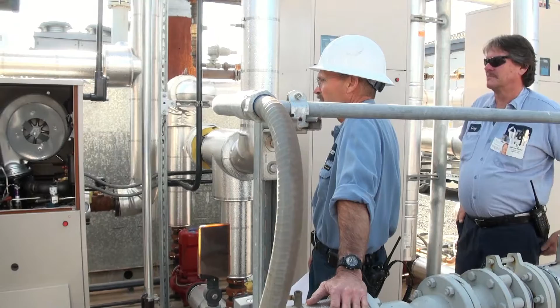Yeah, I know what you're saying, because the pleat is going to get water in it because you're so low at the bottom. So it also relies on the flow of air through the cabinet to cool off the VFD. That's correct, that's exactly what it does. That's why it's in there. It still gets hot, not really hot, but it still requires that to get it all cooled down.